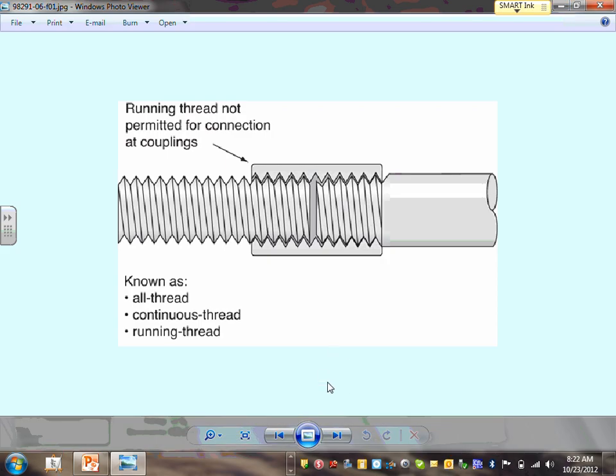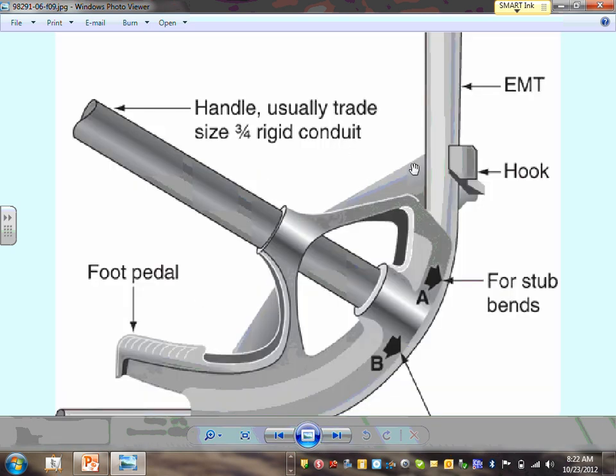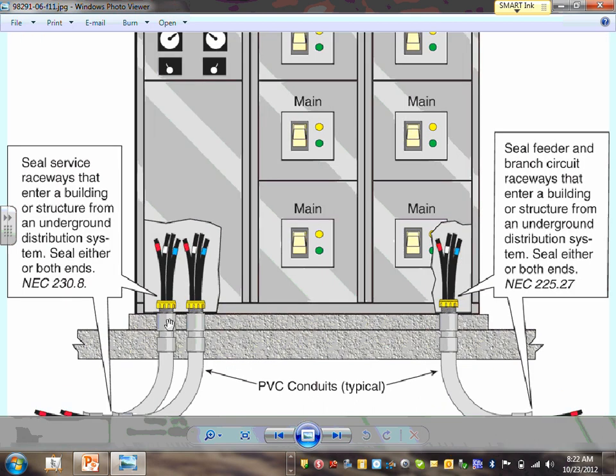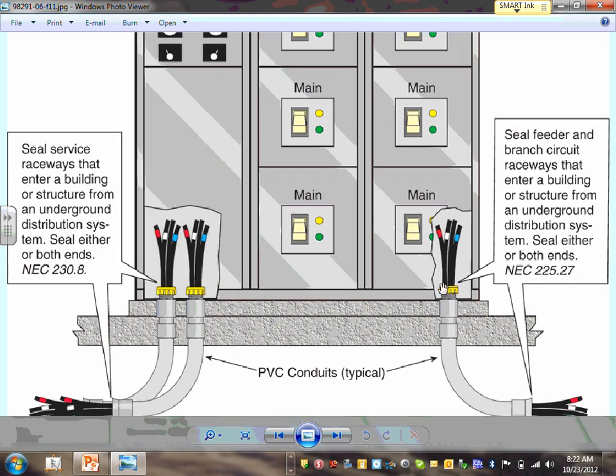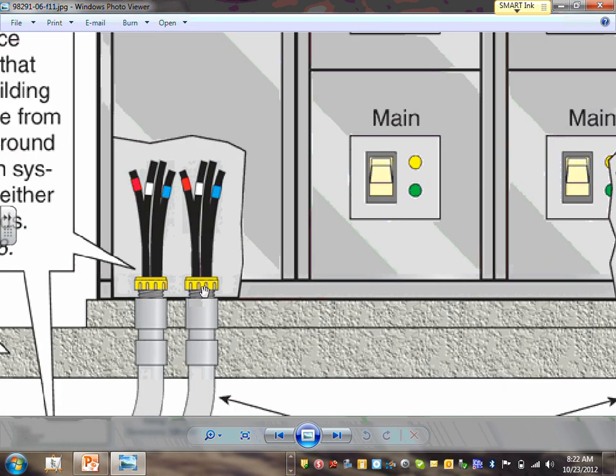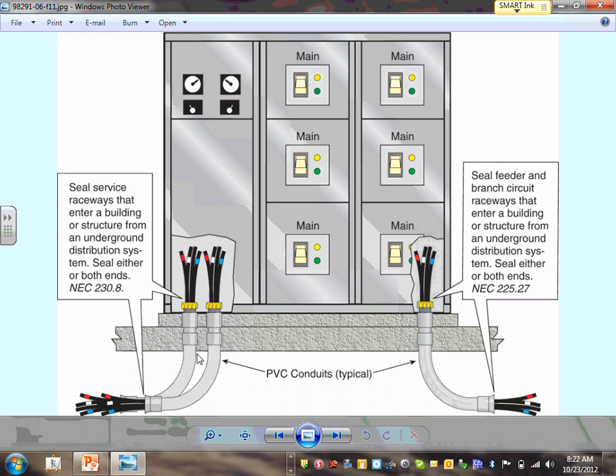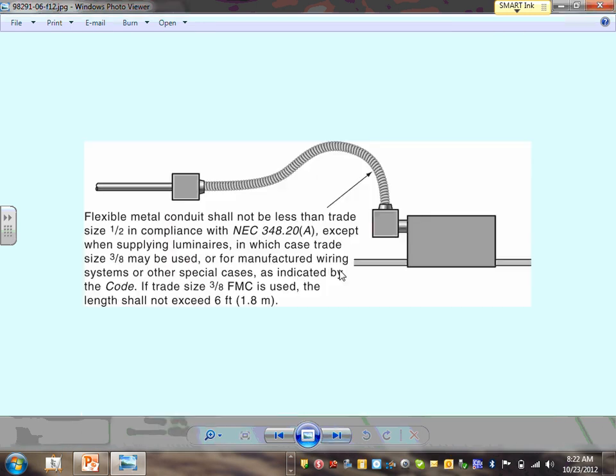A couple more pictures to flash: running threads - don't use them with rigid because they don't give a tight connection. Here's the seal fitting: as you enter the building you have to seal at one or both ends. See that yellow fitting? That's an insulation bushing to protect conductors from being damaged. You also have to put a seal to prevent creatures from getting into the switchgear - that's a code requirement for feeders, branch circuits, and services.